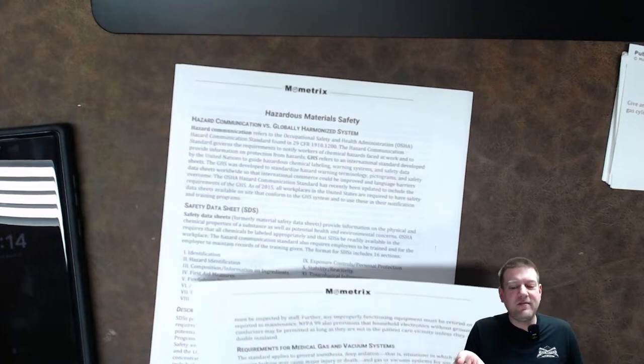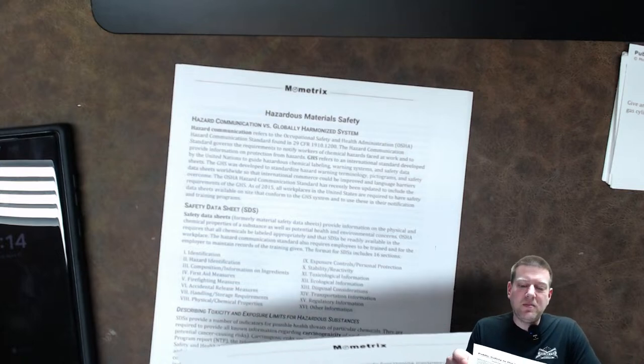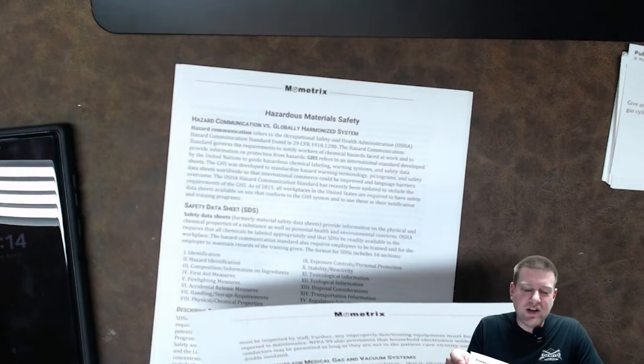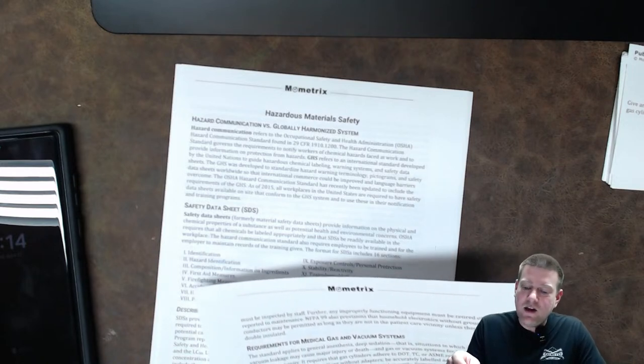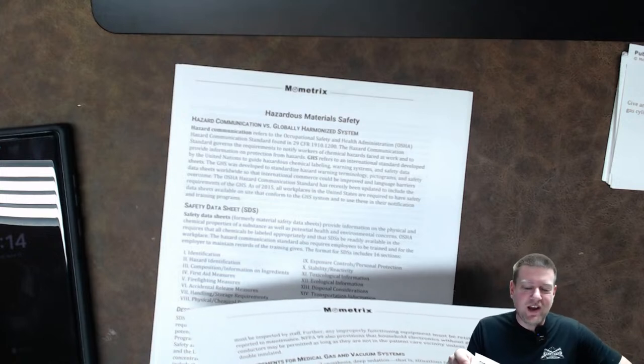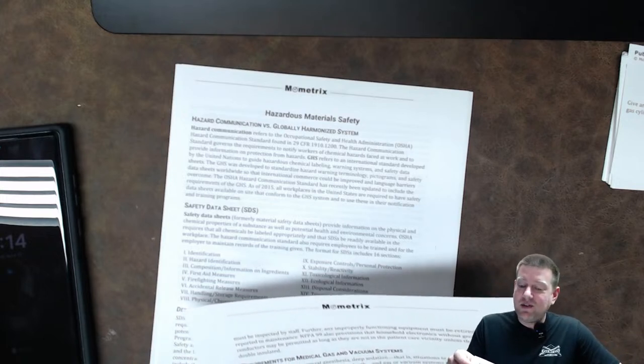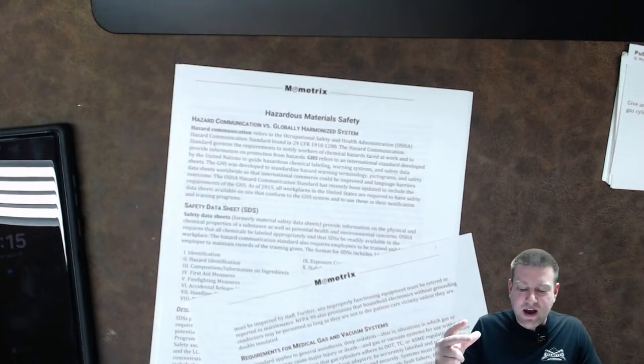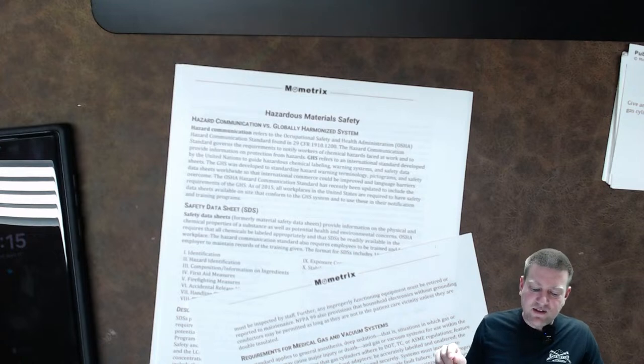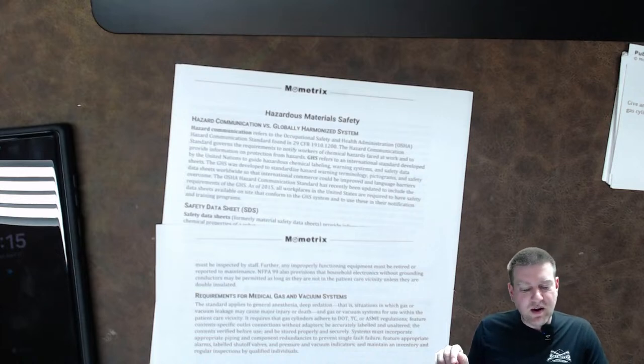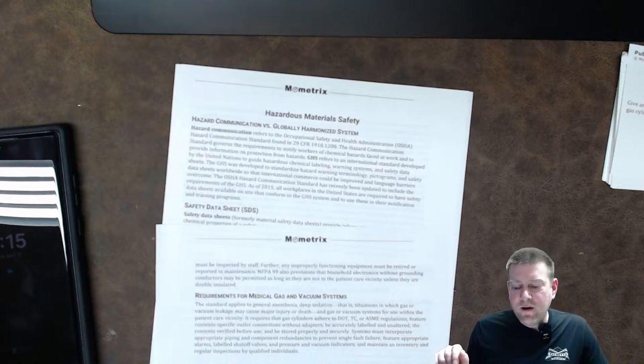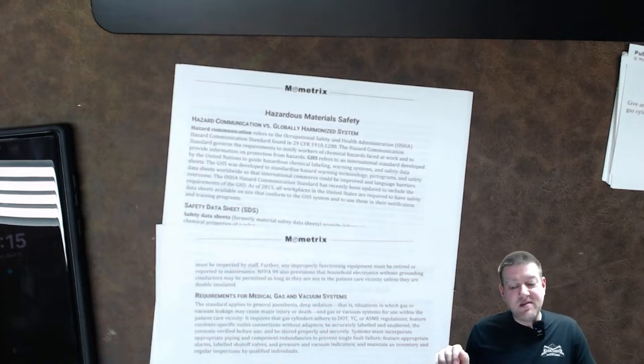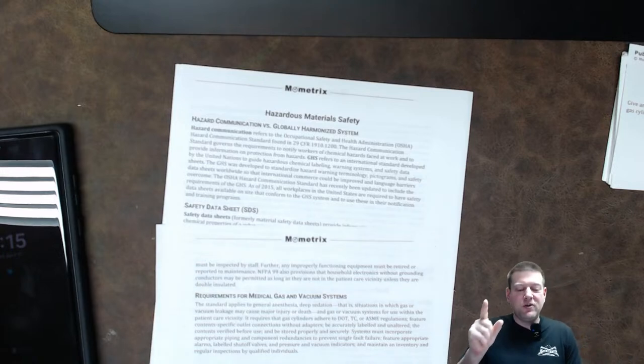Requirements for medical gas and vacuum systems. Here we go. The standard applies to general anesthesia, deep sedation, that is, situations in which gas or vacuum leakage may cause major injury or death, and gas or vacuum systems for use within the patient care vicinity. It requires that gas cylinders adhere to DOT, TC, and ASME regulations, feature content-specific outlet connections without adapters, be accurately labeled and unaltered, the contents verified before use, and stored properly and securely. Systems must incorporate appropriate piping and component redundancies to prevent single fault failure. Feature appropriate alarms, labeled shutoff valves, and pressure and vacuum indicators, and maintain an inventory and regular inspection by qualified individuals.